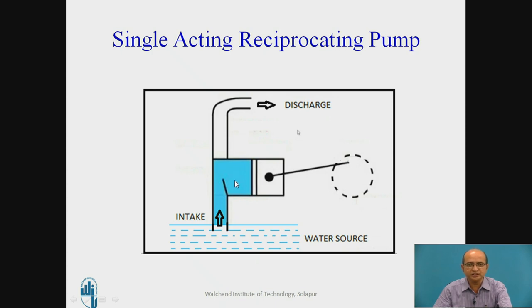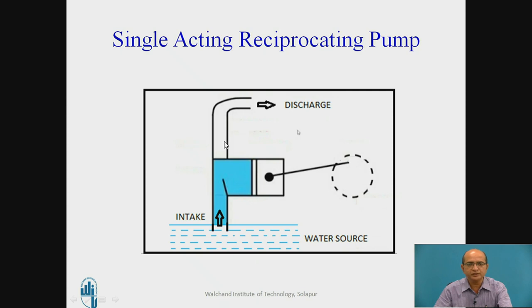This problem of intermittent supply can be overcome by two methods. One is to use a double acting arrangement, and the second is to provide an air vessel. This air vessel is provided on the delivery side. When discharge is occurring, water is stored in the air vessel. When suction is going on and no discharge is occurring, the water from the air vessel rushes to the discharge pipeline. This overcomes the intermittent supply to some extent, but the best method is the double acting reciprocating pump.